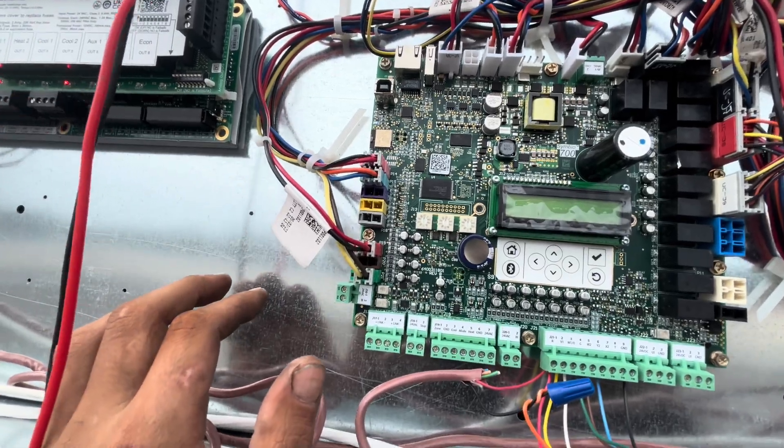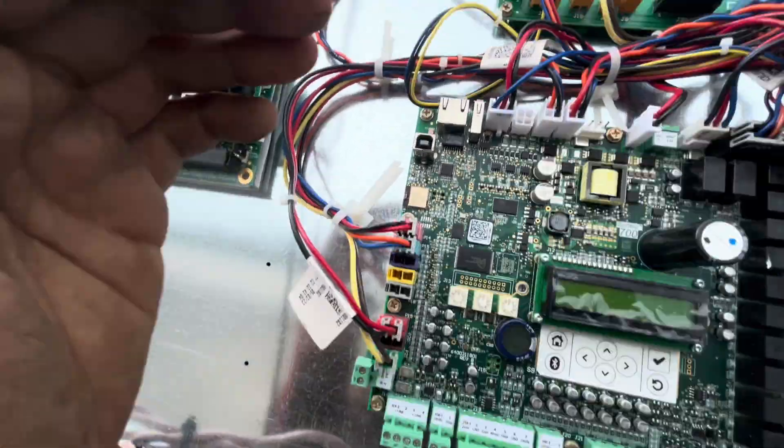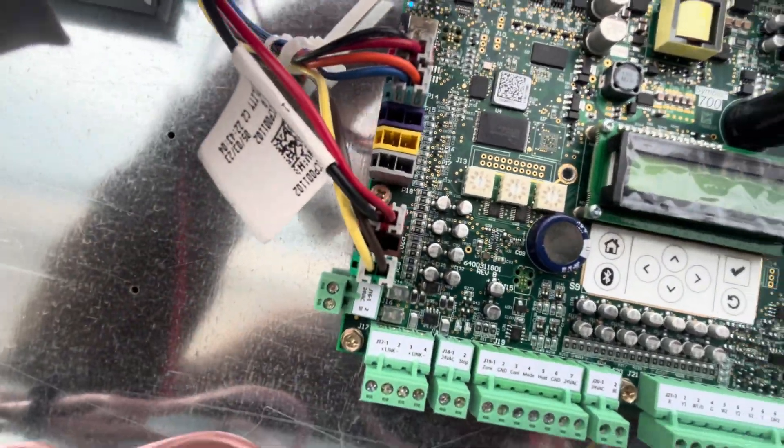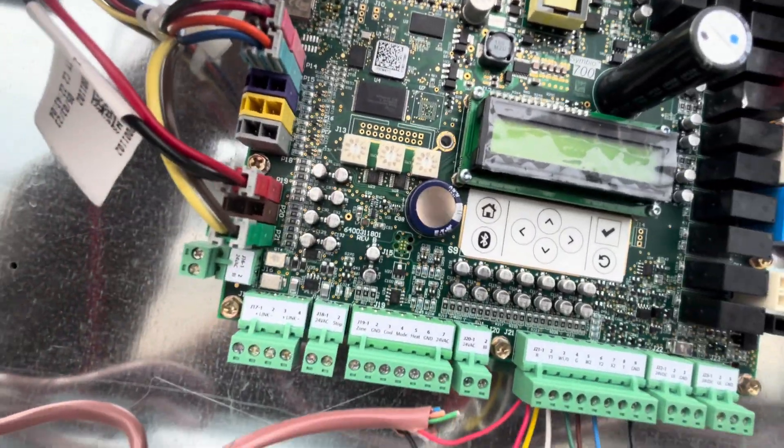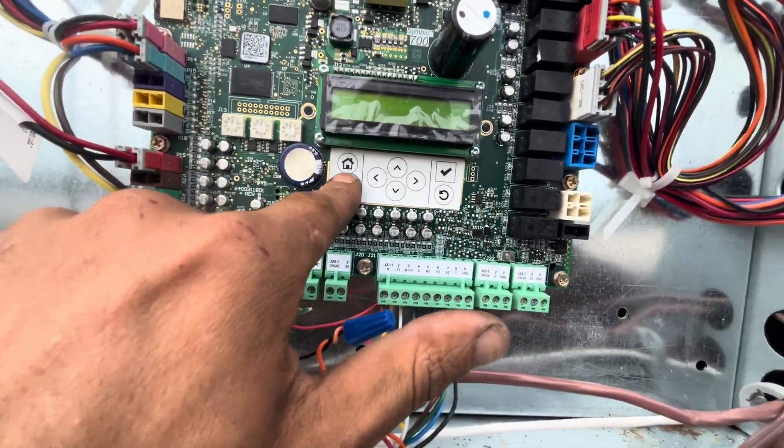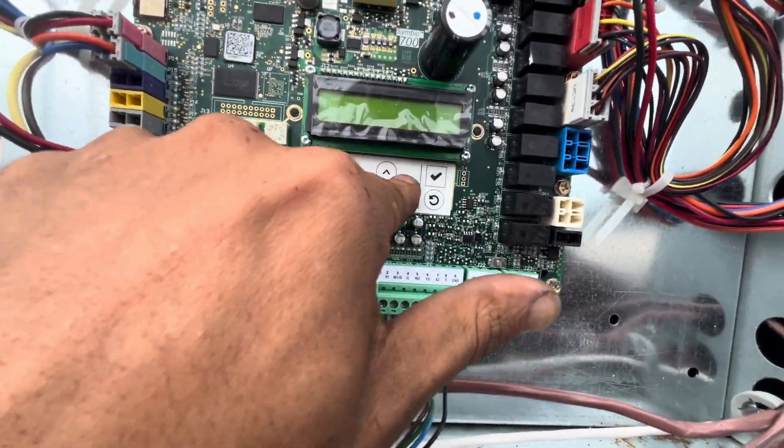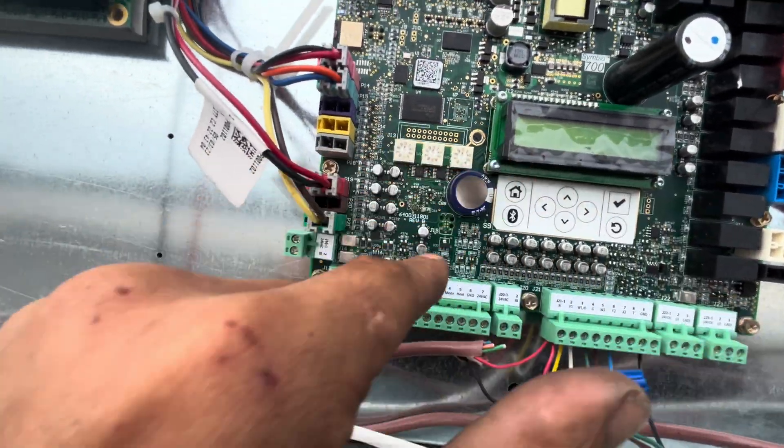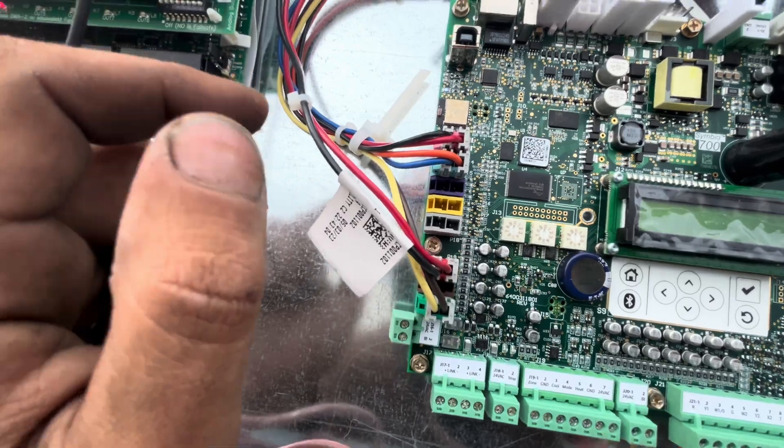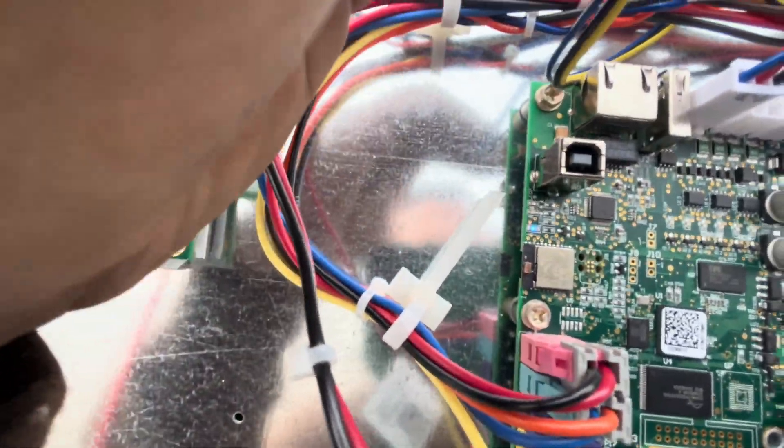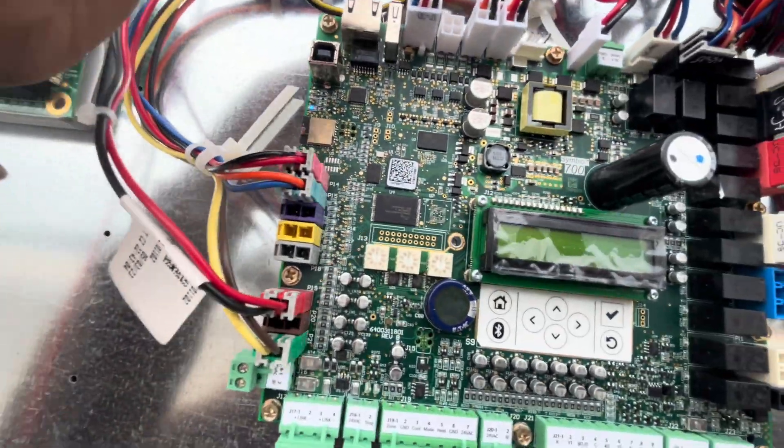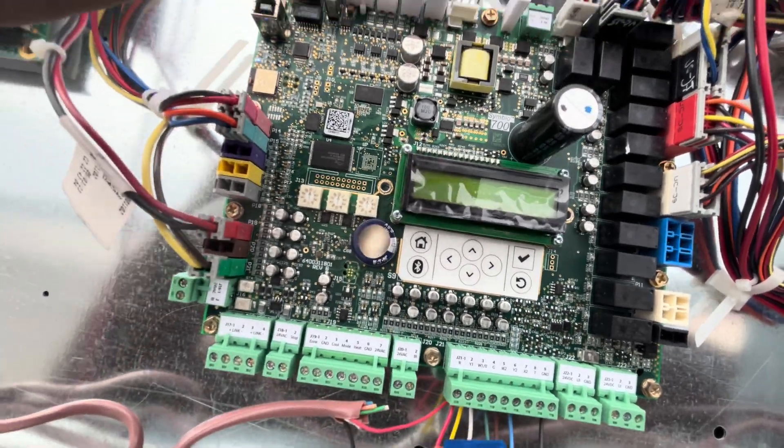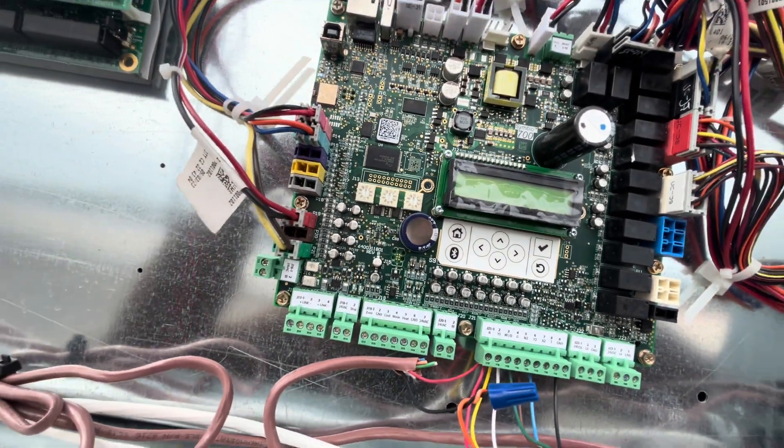So once you plug that connector in and the display goes blank, investigate that circuit. See what's going on with it. See what's causing it in that circuit is causing your board to drop out. So it's that simple, and that's how you diagnose this Symbio 700 board on these Trane units.